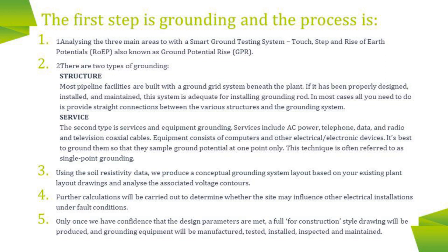3. Using the soil resistivity data, we produce a conceptual grounding system layout based on your existing plant layout drawings and analyze the associated voltage contours. 4. Further calculations will be carried out to determine whether the site may influence other electrical installations under fault conditions. 5.